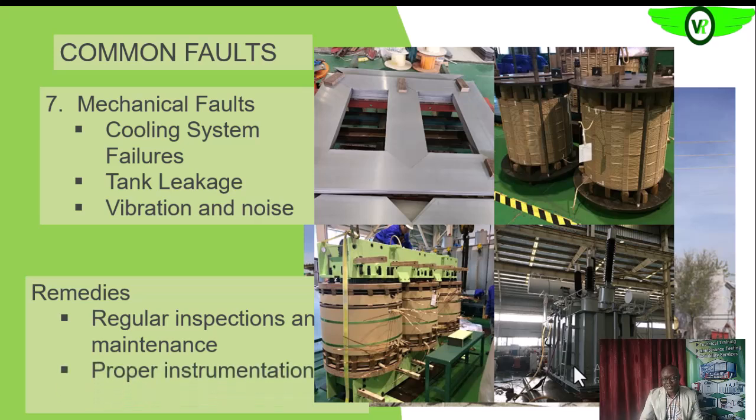Then proper instrumentation too can also assist us. We want to have instrumentation that will be looking at the cooling system, looking at those fans, the oil pump, looking at their operations, and also looking at the level of the oil and even the temperature of the oil. So proper instrumentation will assist us.